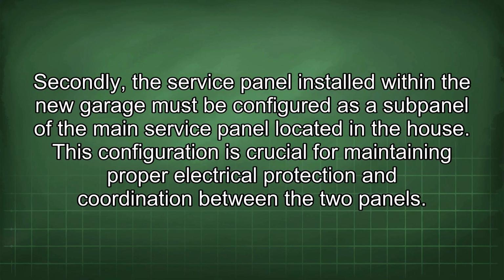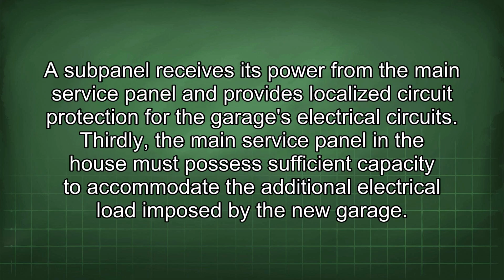Secondly, the service panel installed within the new garage must be configured as a subpanel of the main service panel located in the house. This configuration is crucial for maintaining proper electrical protection and coordination between the two panels. A subpanel receives its power from the main service panel and provides localized circuit protection for the garage electrical circuits.